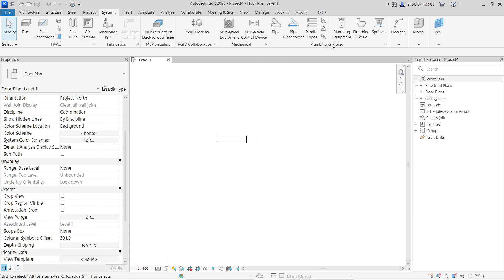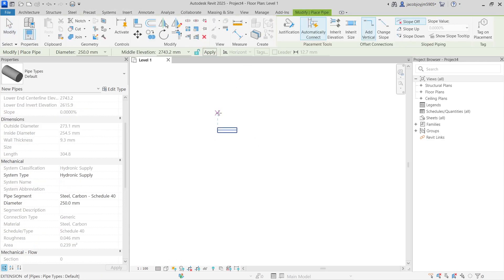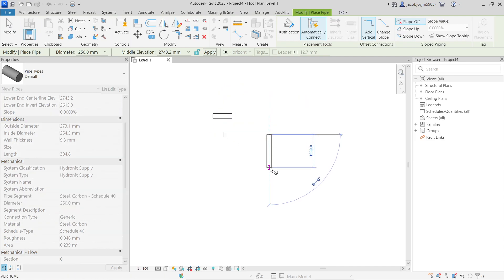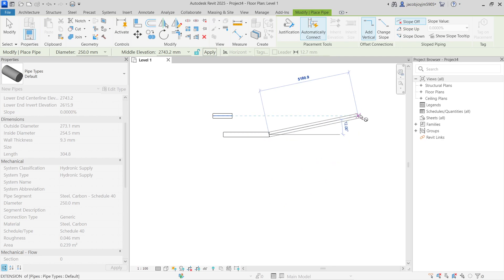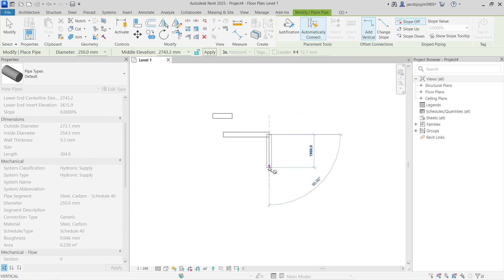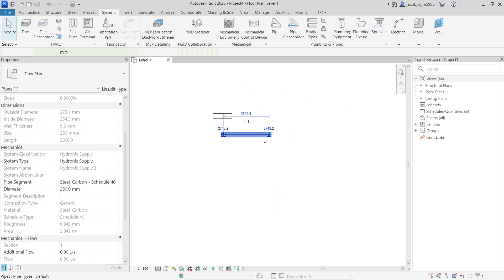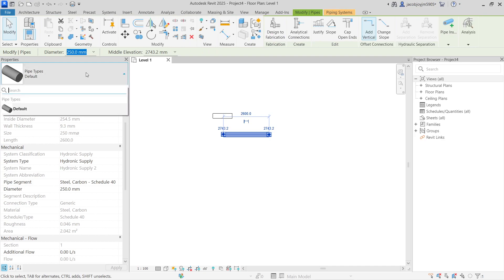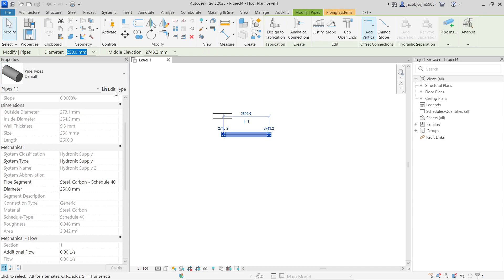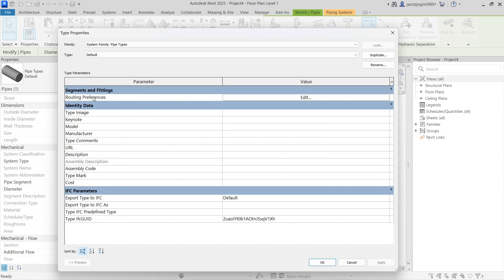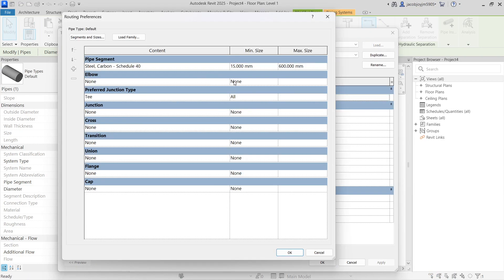Now the pipe is visible. I'm going to go to Systems > Pipe and draw it, but I can't draw the next piece because we don't have any fittings set. If I select the pipe and go to Edit Type, in the Routing Preferences nothing is set — everything is None. That is why we don't get the fittings.